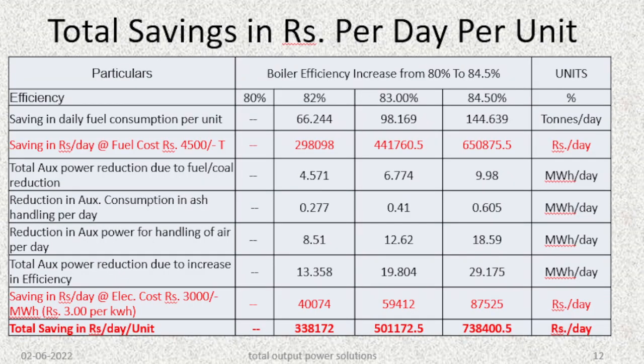Considering all these savings — daily fuel consumption savings, total auxiliary power reduction due to fuel reduction, reduction in ash handling auxiliary consumption, and reduction in auxiliary power for air handling — the total auxiliary power reduction due to the increase in boiler efficiency amounts to around 29.175 MWh per day. At an electricity cost of Rs. 3000 per MWh (Rs. 3 per kWh), this comes out to around Rs. 87,525 per day for the plant.